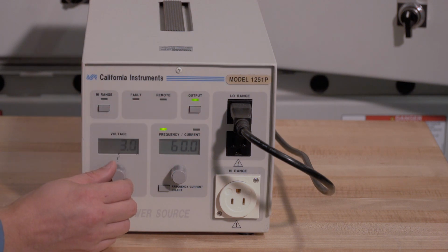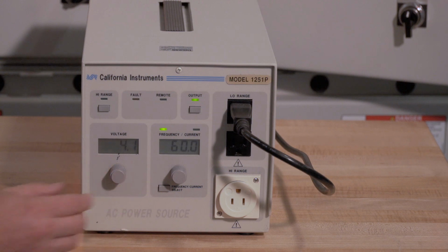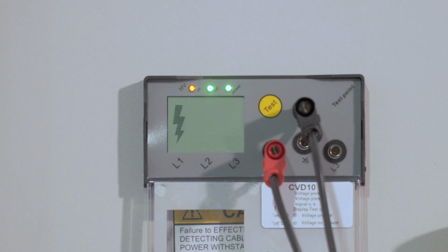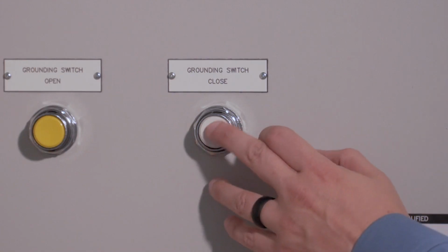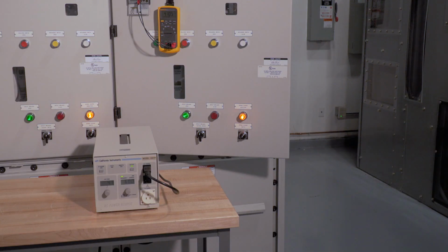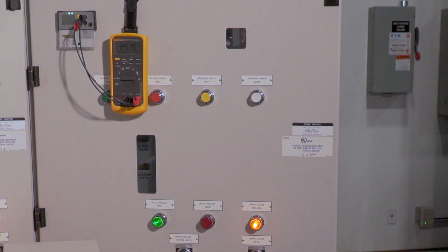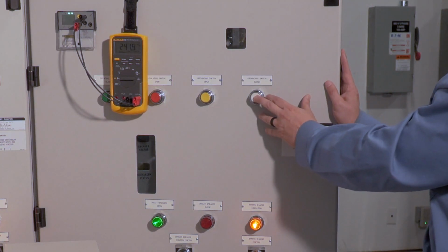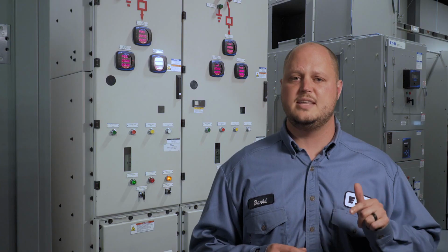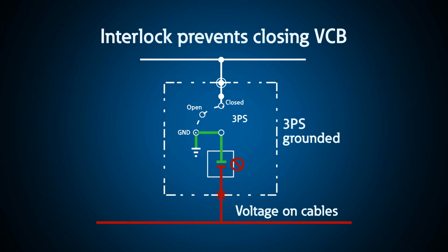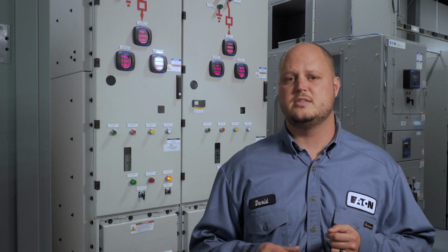I'll now turn on the voltage output and increase the voltage to approximately 4 volts, which will simulate medium voltage on the cable side. You can see that the voltage detection system high voltage red light is on, and at this time I cannot ground the 3-position disconnector switch. I will now turn off the voltage, and I can now ground the 3-position disconnector switch. The second prevents the closing of the circuit breaker when the 3-position switch is grounded if voltage is detected in the cable compartment. This also prevents the operator from creating a ground fault.